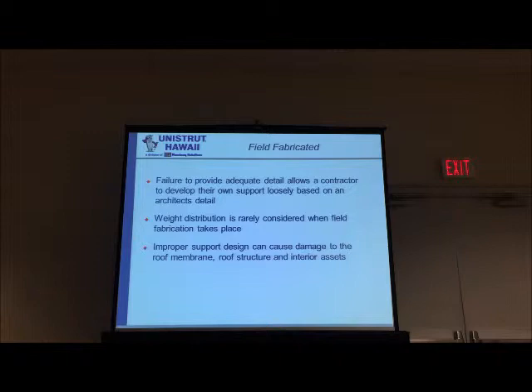You do not want to exceed 2 pounds a square inch loading on a non-penetrating roof support. It's basic math, is it not? You take the surface area of your base, you take the weight of the equipment or service being loaded onto your roof, and when you divide that weight into the square inches of your base, the number cannot come out any more than 2.